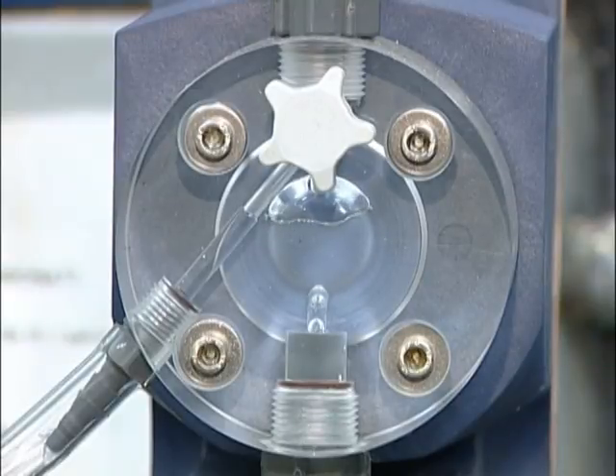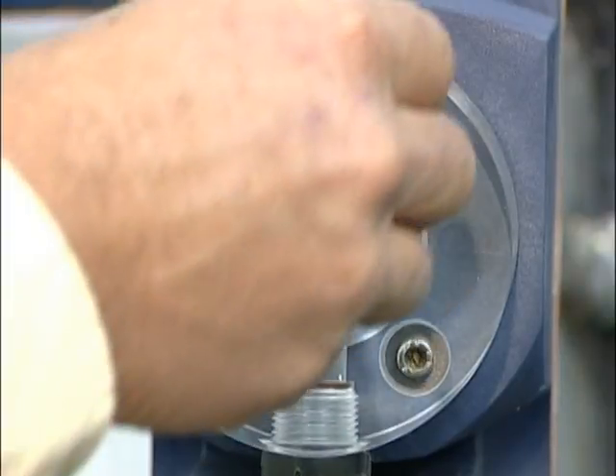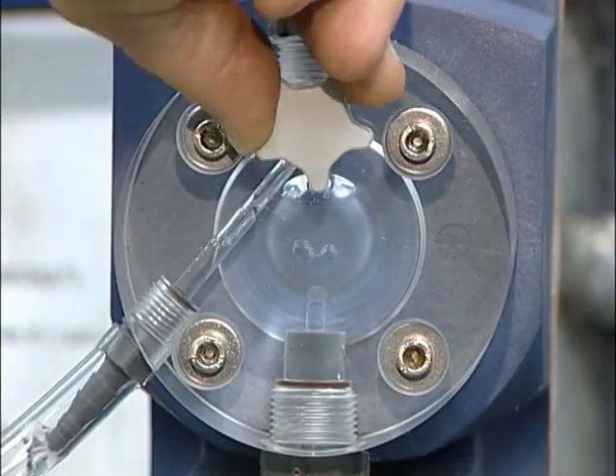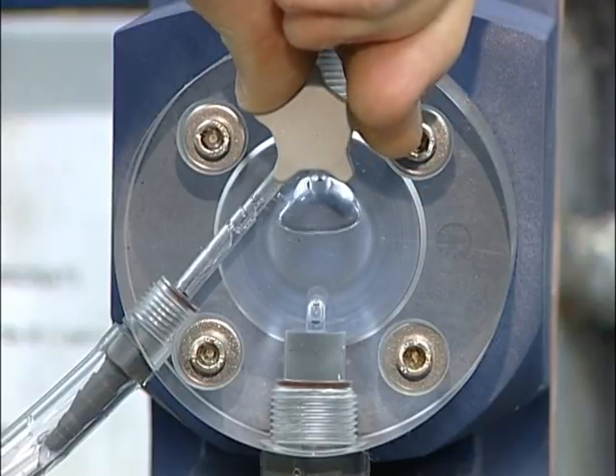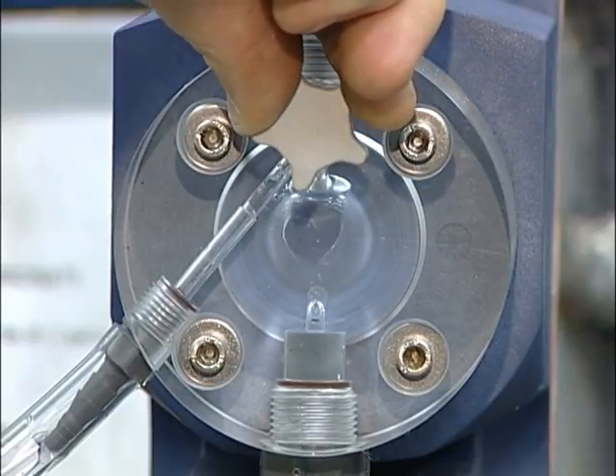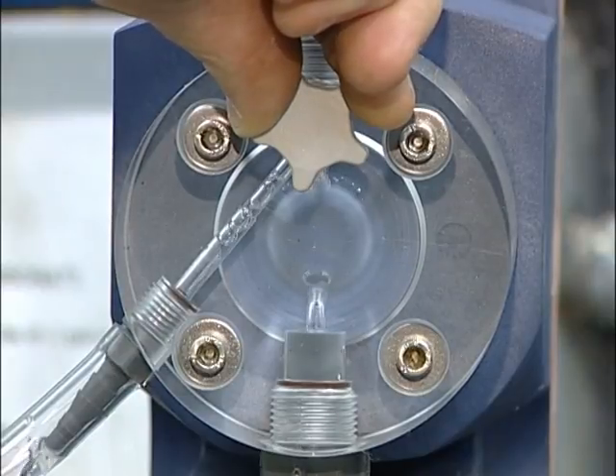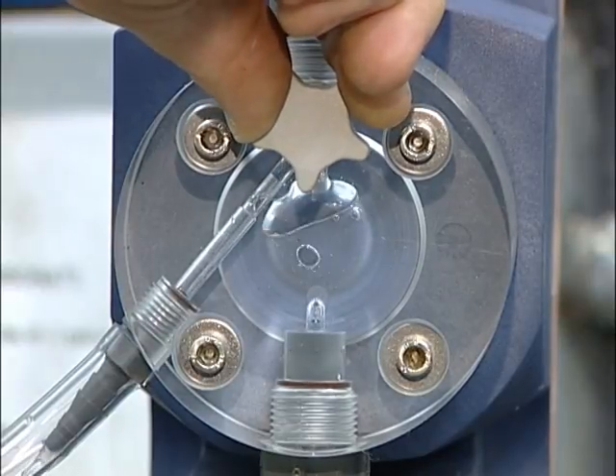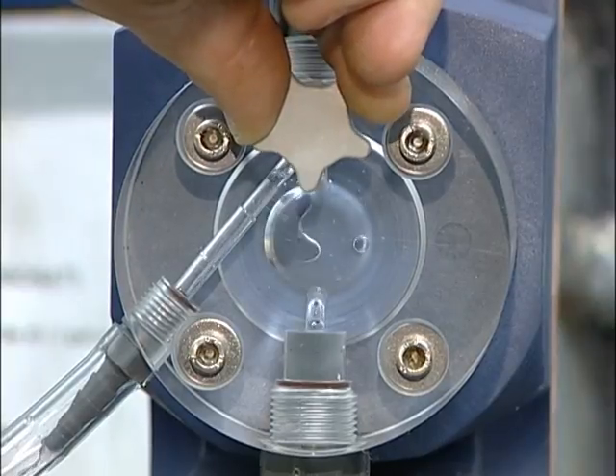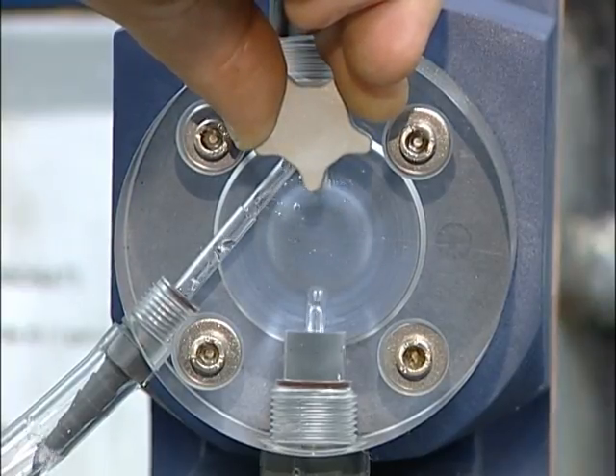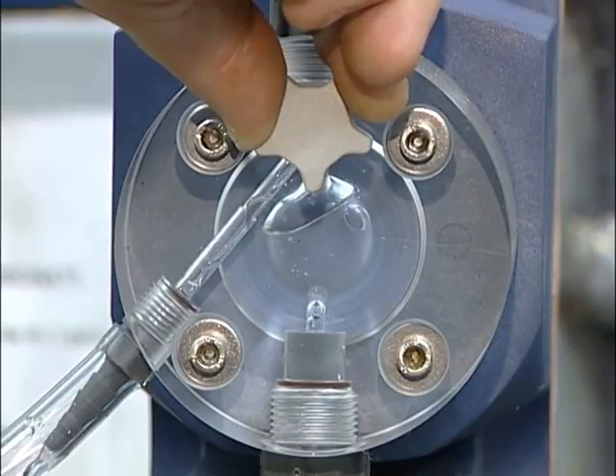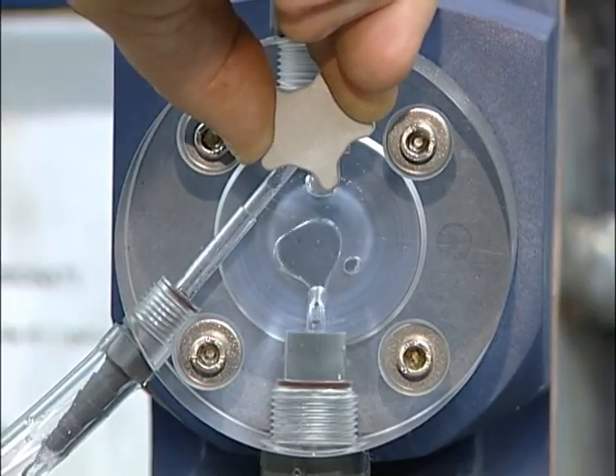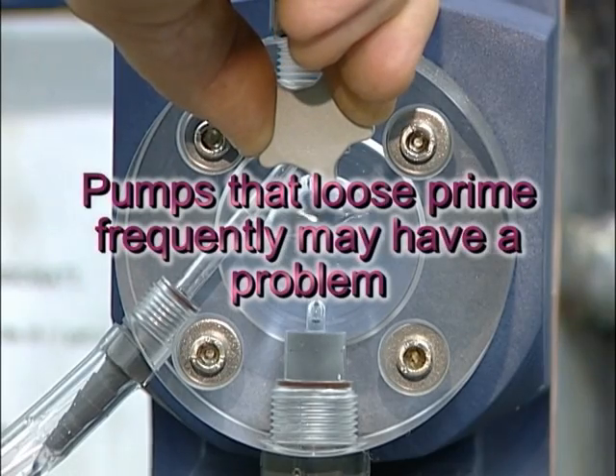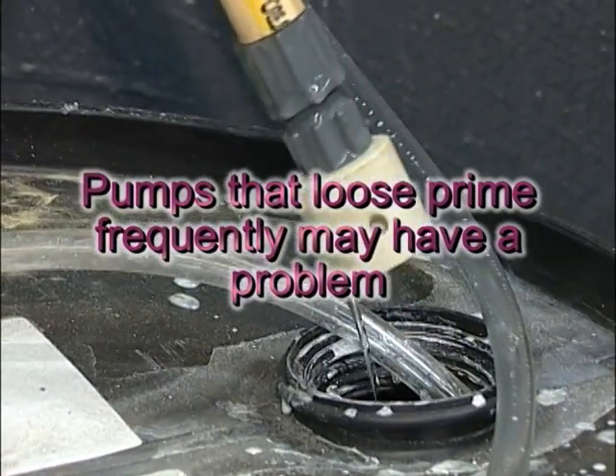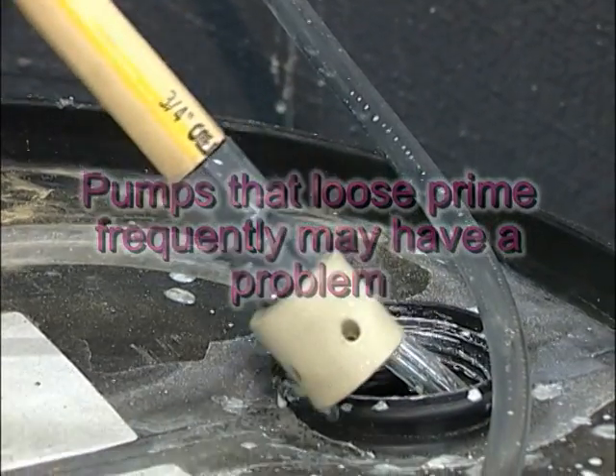One of the symptoms of lost prime is a louder than usual sound made by the diaphragm during operation. Once the pump loses prime, it will need to be primed manually. This can be accomplished by relieving the pressure on the outlet of the pump, making it easier for the pump to draw the chemical into the feed line. Once the pump has been primed, it should continue to operate automatically. A pump that loses prime frequently may have a crack in the line or some other problem that allows the fluid to drain.